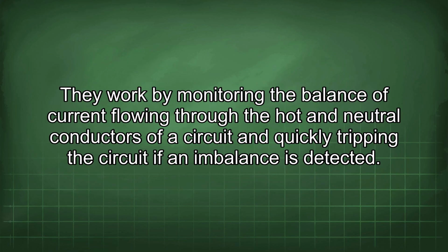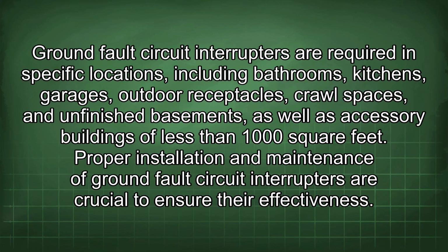They work by monitoring the balance of current flowing through the hot and neutral conductors of a circuit and quickly tripping the circuit if an imbalance is detected. Ground fault circuit interrupters are required in specific locations, including bathrooms, kitchens, garages, outdoor receptacles, crawl spaces, and unfinished basements, as well as accessory buildings of less than 1,000 square feet. Proper installation and maintenance of ground fault circuit interrupters are crucial to ensure their effectiveness.